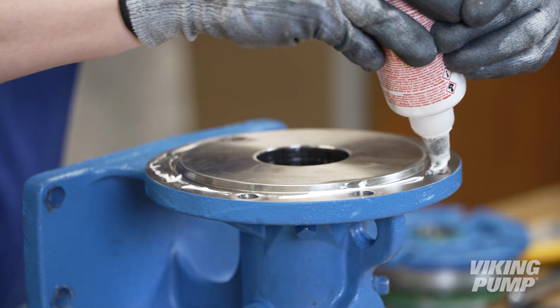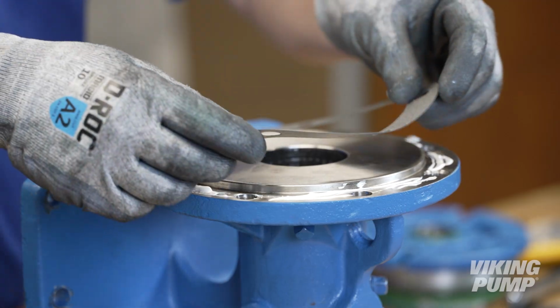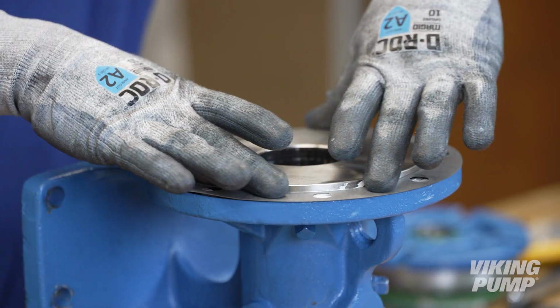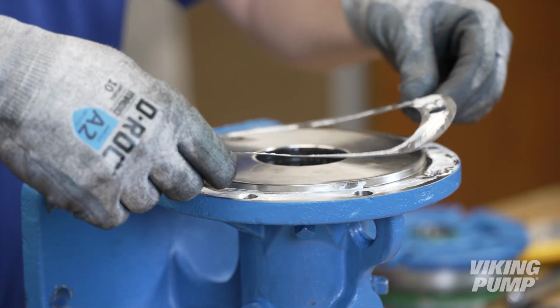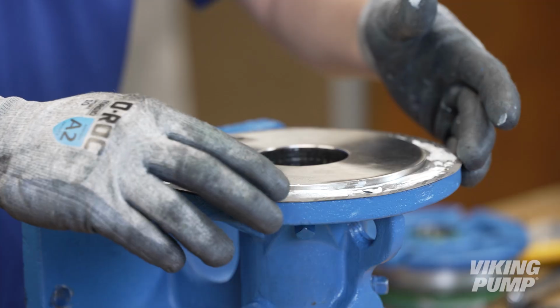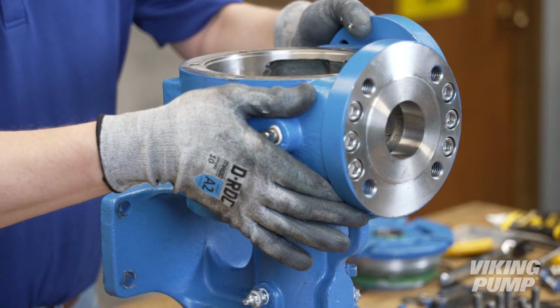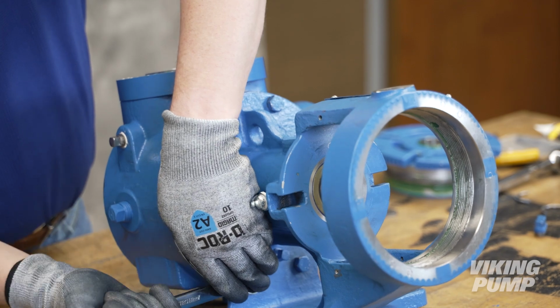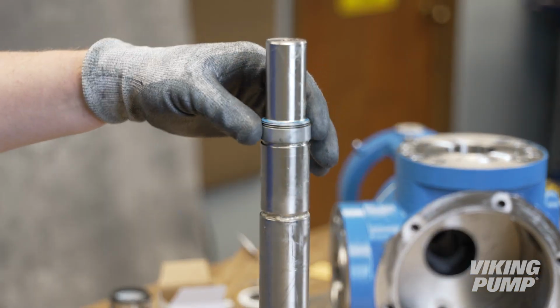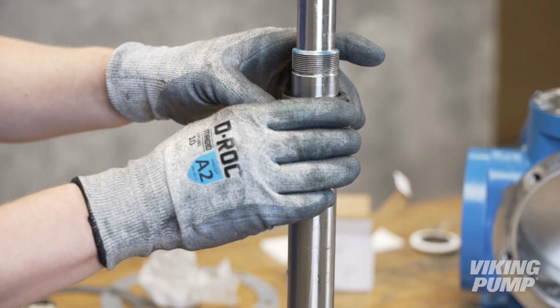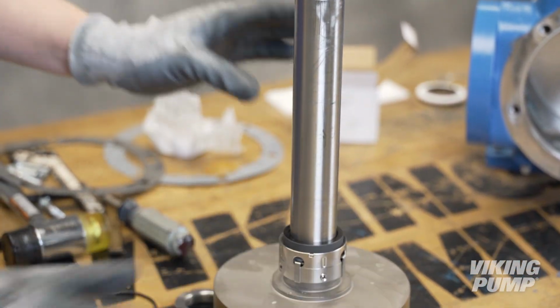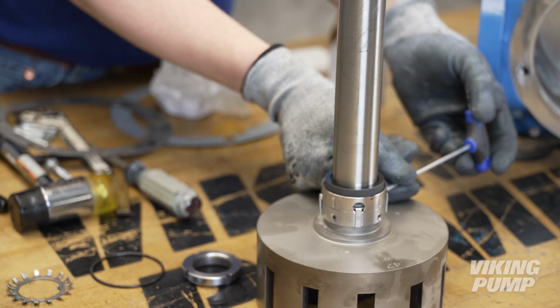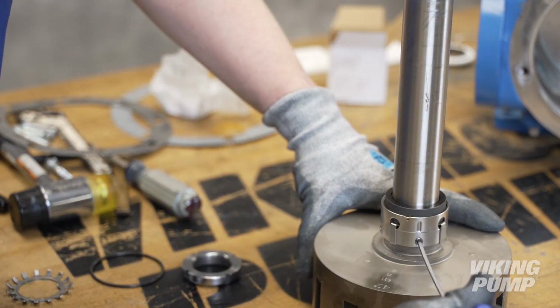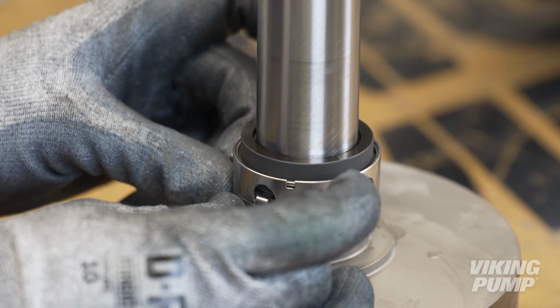Install the bracket gasket. Apply appropriate gasket sealant to the bracket and ensure even coverage on both sides of the gasket. Install the casing. Install the seal installation sleeve onto the shaft. Lubricate the shaft and install the seal rotary member until it makes contact with the back of the rotor. Tighten each set screw until they just make contact with the shaft, then fully tighten the set screws. Remove the seal clips to engage the seal.